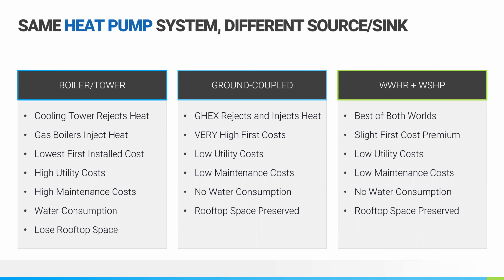With the ground coupled option, instead of a cooling tower and boilers, you have an underground heat exchanger rejecting and injecting heat. That comes with very high first costs due to the drilling required. But you'd see lower utility costs, much lower maintenance costs, no fresh water consumption, and preserved rooftop space. Still, the first cost was something this municipal utility couldn't get over.